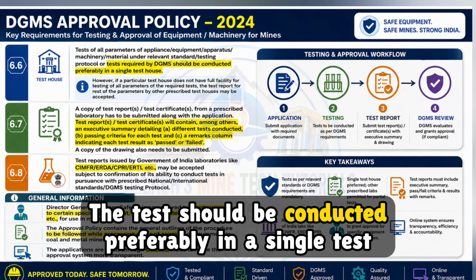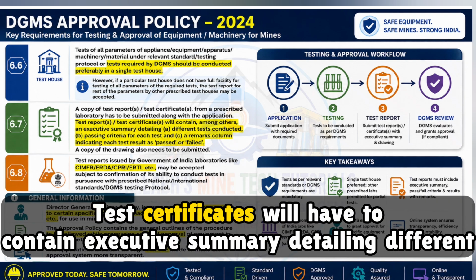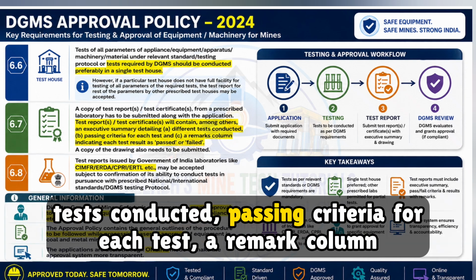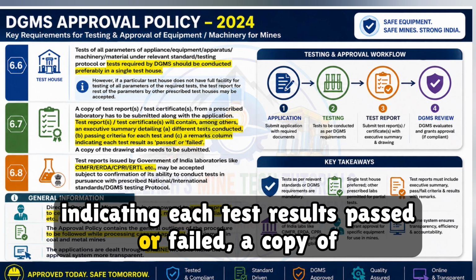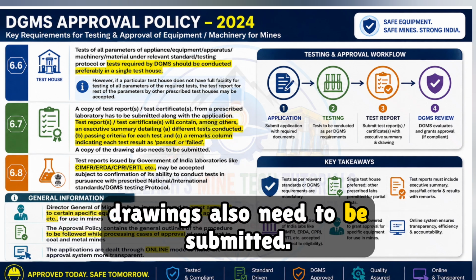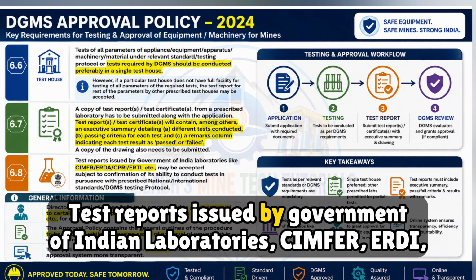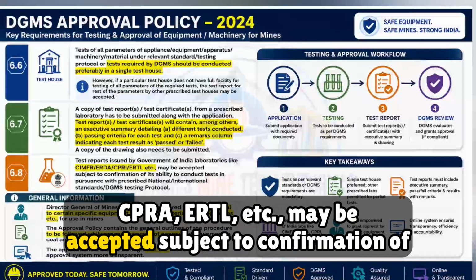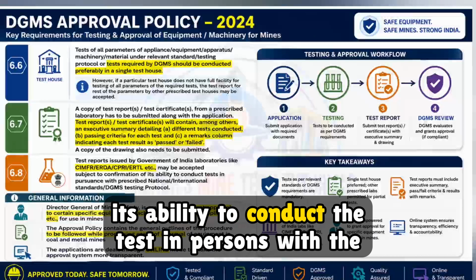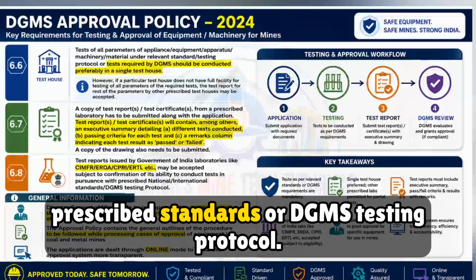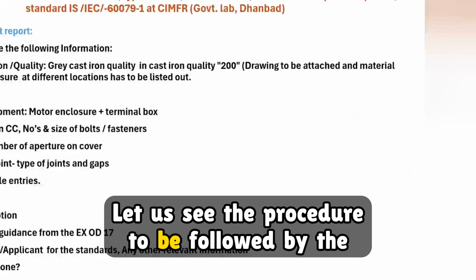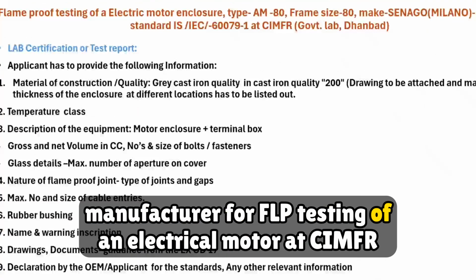The test should be conducted preferably in a single test house. Test certificates will have to contain an executive summary detailing different tests conducted, passing criteria for each test, and a remark column indicating each test result passed or failed. A copy of drawings also needs to be submitted. Test reports issued by Government of India laboratories, CIMFR, ERDA, CPRI, ERTL, etc. may be accepted subject to confirmation of their ability to conduct the test in pursuance with the prescribed standards or DGMS testing protocol.